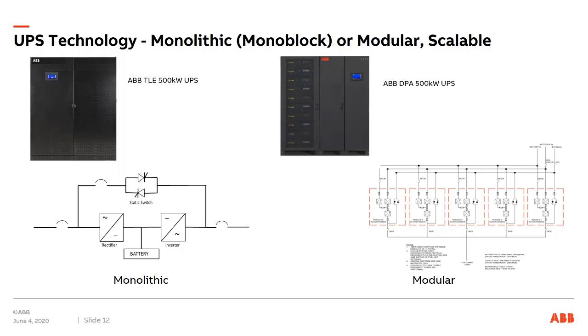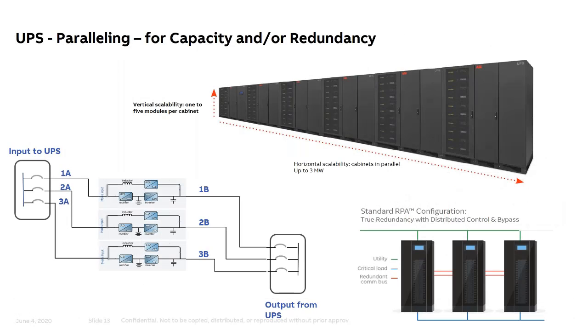There are a number of different designs out there from different manufacturers of both monolithic and modular UPSs. And regardless, as I mentioned already, all the UPSs can be paralleled. So this big black train in the top right corner actually shows 6 modular UPSs in parallel. So 6 times 500 would support 3 MVA of power. It doesn't happen often, but it's possible. All of the UPSs, regardless of size, can be paralleled.